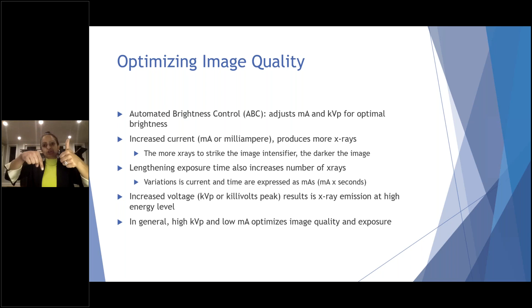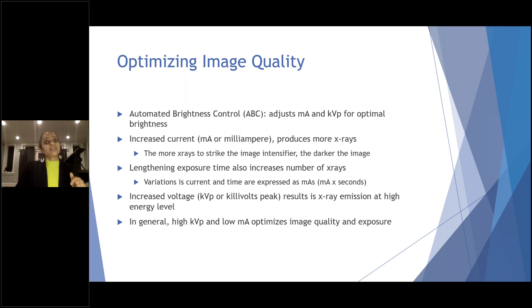So then when you increase the voltage, which is the KVP aspect, this results in X-ray emission at high energy level, so that penetration. In general, our ABC modes are having a high KVP and a low MA to optimize our image quality as well as exposure. Really, I'm not going to go into much more than that because our machines are smart enough to do that for us. That's why you don't see, other than maybe in the thoracic spine, et cetera, that you may need to play with the image quality a little bit.